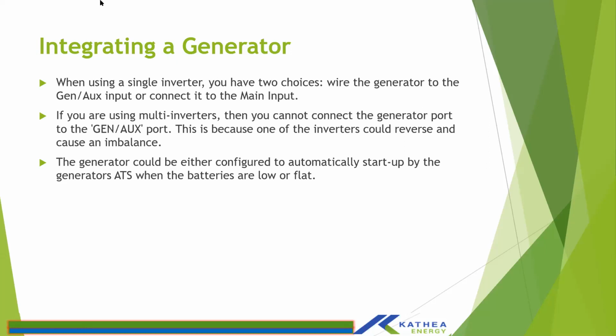Brian? Yes. Just a question quickly about the integration of the generator. Yes. If you do a changeover and you connect the generator to the main input, and the inverter is set up to feed back to the grid. Yes. What happens in that instance? Because obviously a generator doesn't want to have feedback power.